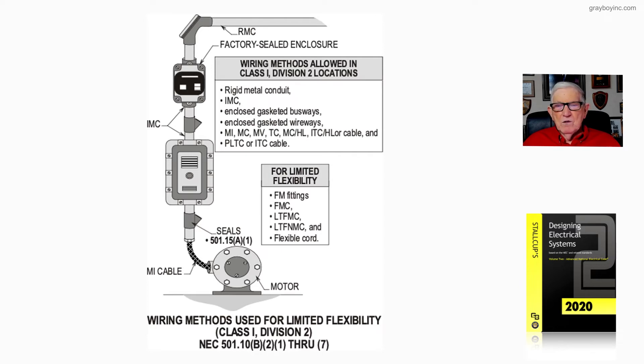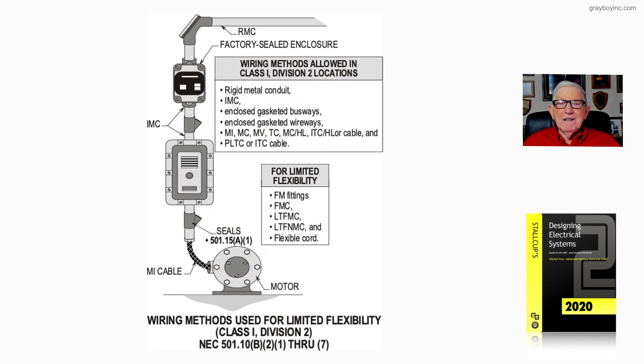We could use flexible cord under certain conditions, and notice you would need a seal there. But if it's MI cable, then you wouldn't necessarily need a seal unless the engineer specifies one.